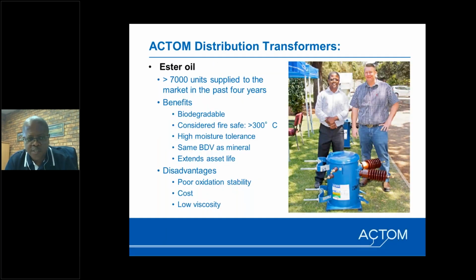We also manufacture ester oil transformers. We currently have a fleet of over 7,000 transformers supplied, most of which are to Eskom, because Eskom has now migrated from mineral oil to esters, and they're now 100% taking transformers with just ester oil. And the benefits of using ester oils is that the oil is biodegradable. The raw material of the oil is sourced locally from the farmers, and the facility that manufactures the oil is also found locally. It's about 7 kilometers from our factory.